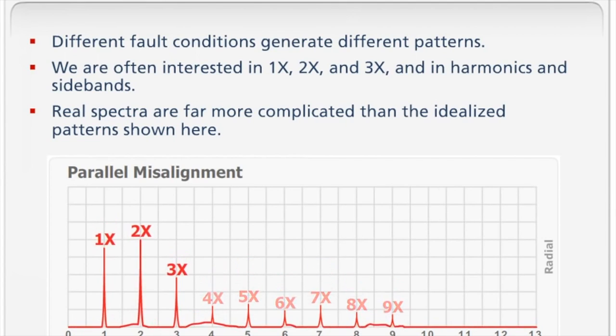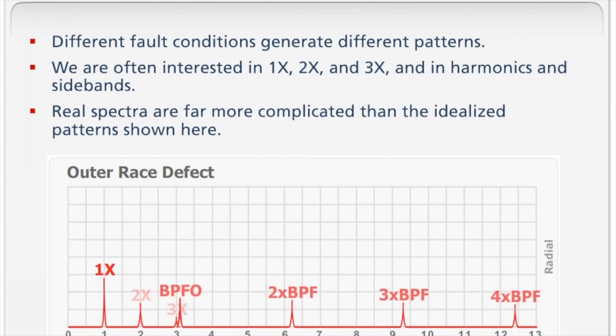When you see patterns like this, or patterns like that, or patterns like this for bearings, you won't just think of the wall chart. You'll think, aha, harmonics, what does that tell me? Sidebands, what would that tell me? Lots of peaks, high amplitude, low amplitude, all these patterns should tell you what must be happening inside the machine in order to create those patterns. And that, in my opinion, is how you become a good vibration analyst.